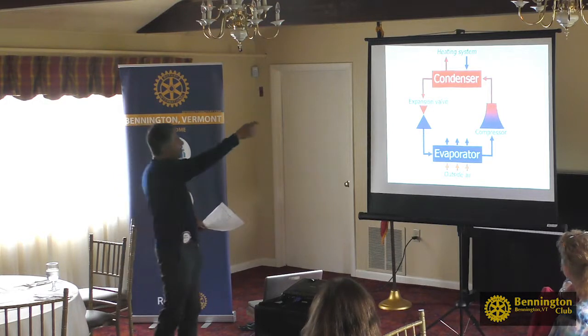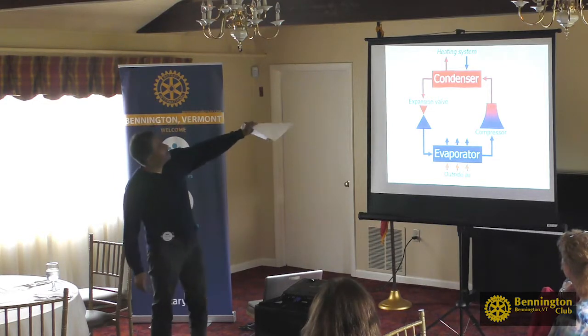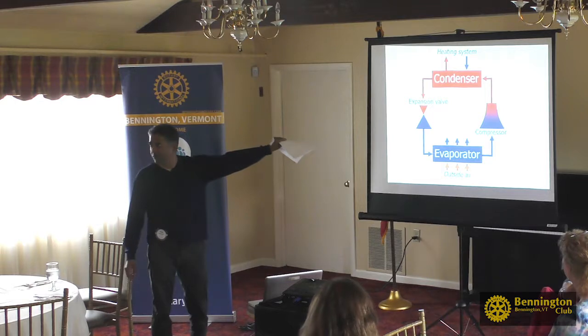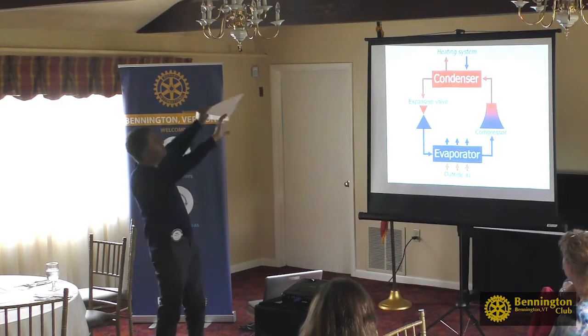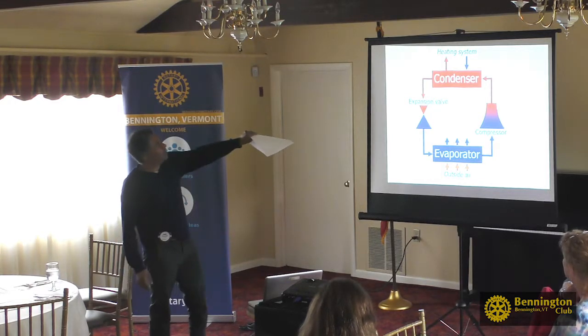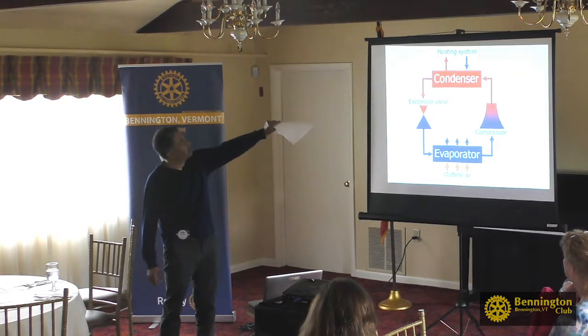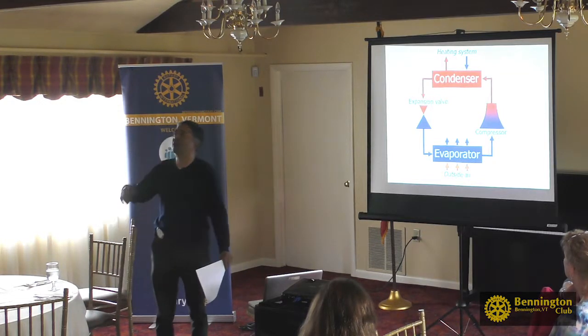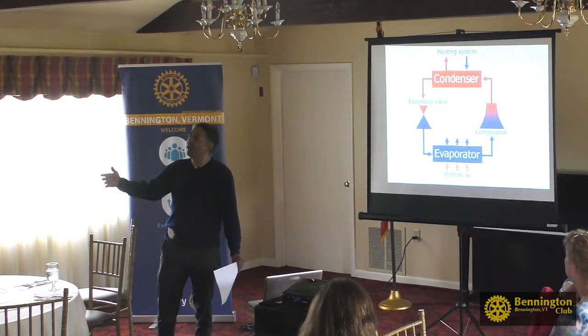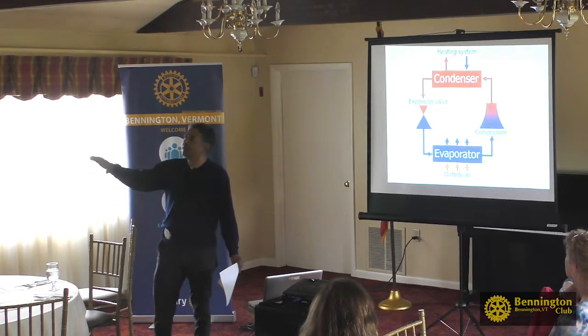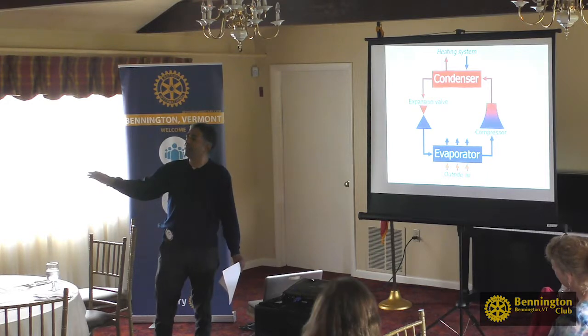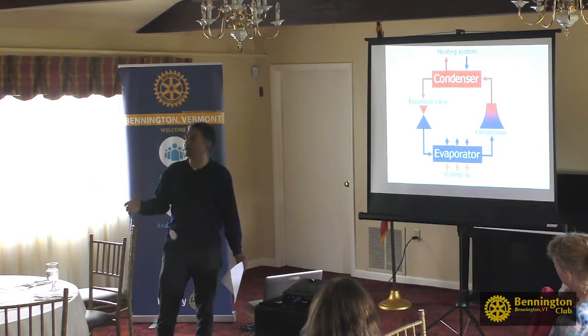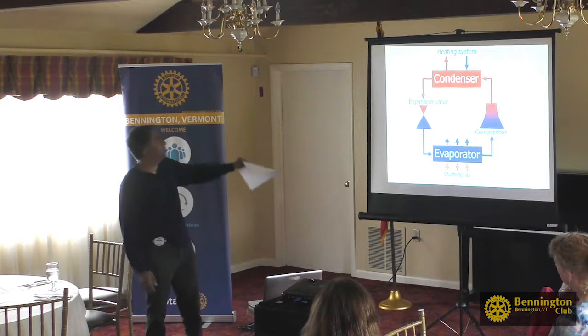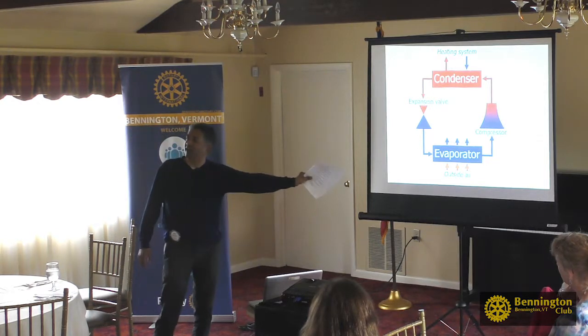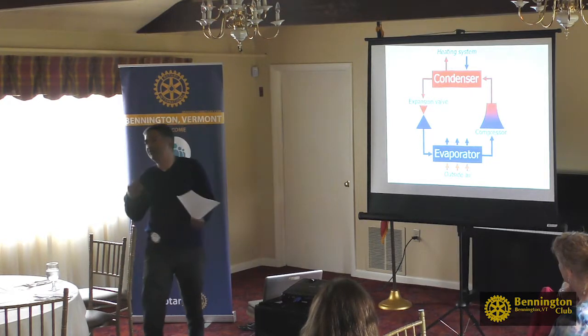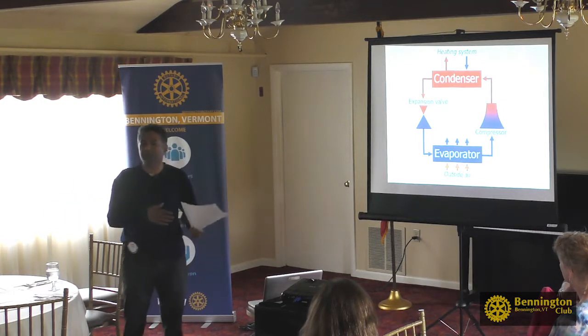So start anywhere in this closed loop process. That condenser, assume it's inside the room right now - that's that thing up on the wall. You've got hot gas refrigerant vapor coming into the condenser, which is hotter than your room, and when the fan blows across it, it blows the heat into the room. The hot gas condenses and becomes a warm liquid. Then it goes through this expansion valve, which engineers call a Joule-Thomson expansion.